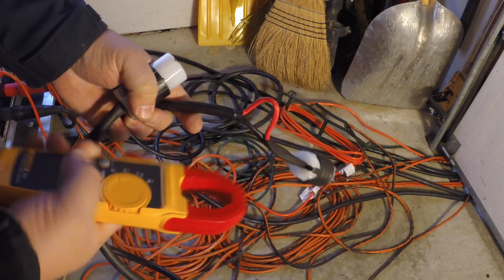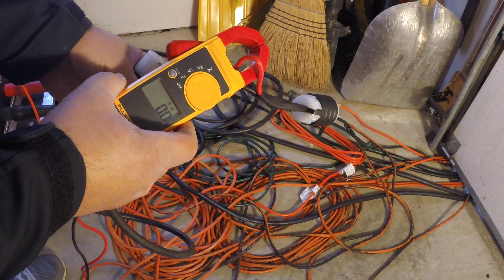The purpose of this is, I turn every single light on, so the controllers are basically running at full blast, everything is on. Then I'll take my clamp meter and plug each controller into this and then into its receptacle. I'll put the clamp meter around it and make sure the extension cord is not drawing more than it's rated for.